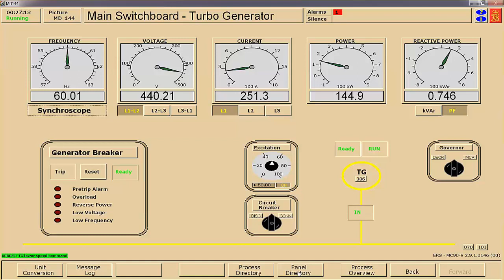So there we go. Now, the next thing I'm going to do is bring up on this screen, so you can see it, diesel generator number 2, and then on my other, I'm going to put up number 1. Now I'm going to be transferring the load off diesel generator number 2 to number 1. All right, so the same process. I'm going to decrease and increase. Decrease number 2, increasing on number 1, trying to keep it at 60 hertz or close to it. I'll do a double click on this one to bring that up a little bit. There we go, decrease.